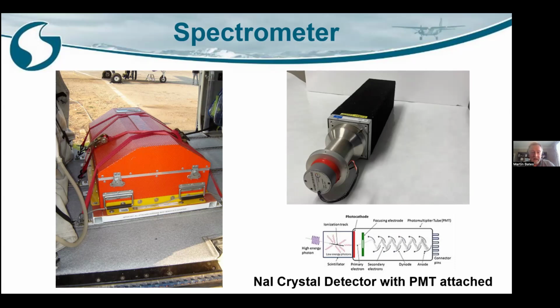The thing in the black box is actually a thermal wrapping around a sodium iodide crystal. This crystal is doped with thallium and it scintillates. It emits a photon of light for each gamma, of an intensity related directly to the incident gamma ray energy. So you have a relationship between the gamma ray energy and a photon of light.